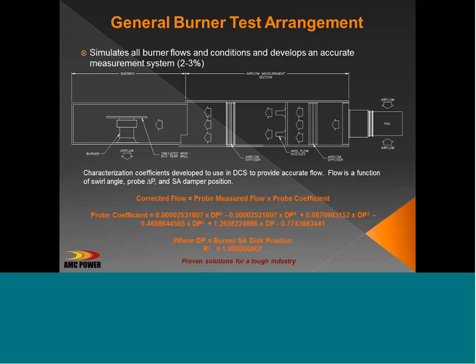So Air Monitor uses a variation on its VoluPro pitot tube, and we've put pretty much every low NOx burner on the market in our wind tunnel back in Santa Rosa, California, and we've developed flow measurement accurate to within 2 to 3% for every burner type out there. A few slides ago, I showed that velocity is equal to the square root of velocity pressure over density, a very simple formula.